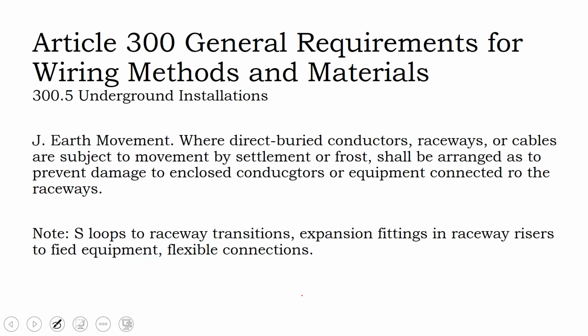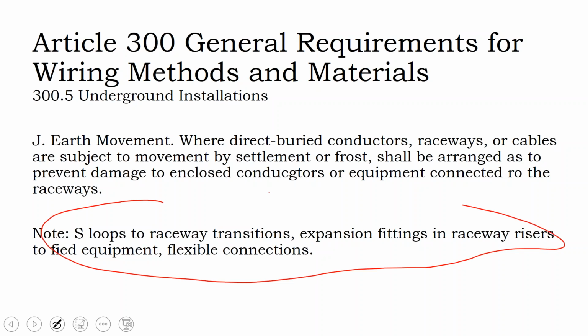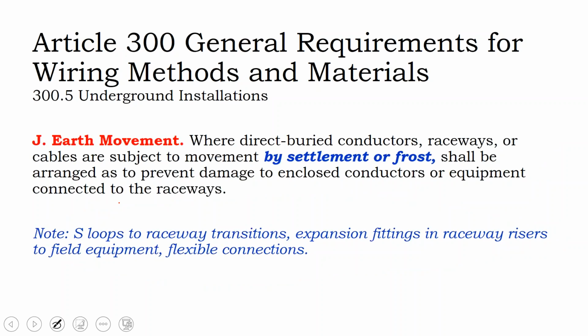You need to protect the burial cables from earth movement. And so you may need to give yourself some slack in your cable when you come up from the earth. I'm using S-loops to transition in raceways, expansion fittings. So you're using these drip loops not just to get water off the wire, but also to give it some flexibility so you don't pull your wire apart with seasonal changes.